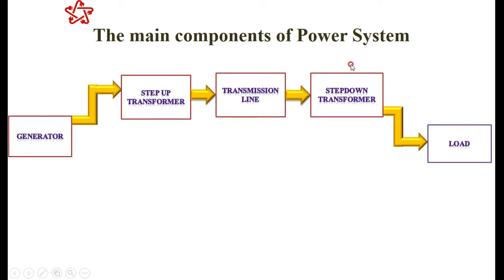At the step-down level, once the voltage reaches the load centers, it is stepped down from around 138 kV to 34.5 kV. Then 34.5 kV can be further reduced to popular voltages — 433 V three-phase and 230 V single-phase. These are the three main components of the power system seen in the overall power system.